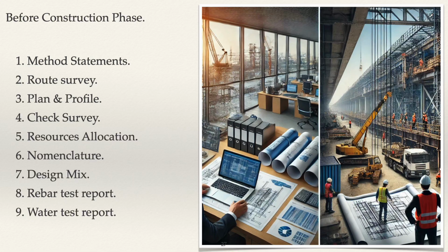3. Plan and profile provides a detailed graphical representation of the transmission line route, including vertical and horizontal profiles, tower locations, elevations and distances between towers, ground clearances, and conductor sag and tension specifications. It acts as a base document for foundation design, tower erection, and stringing.